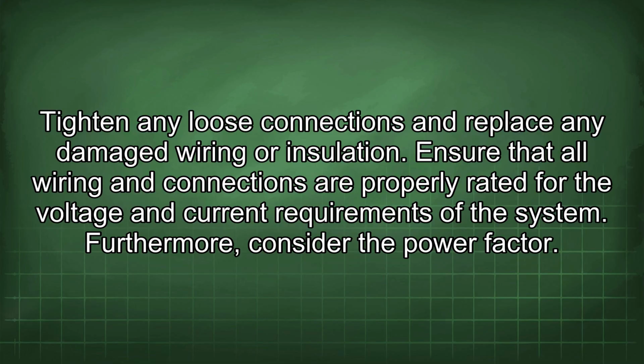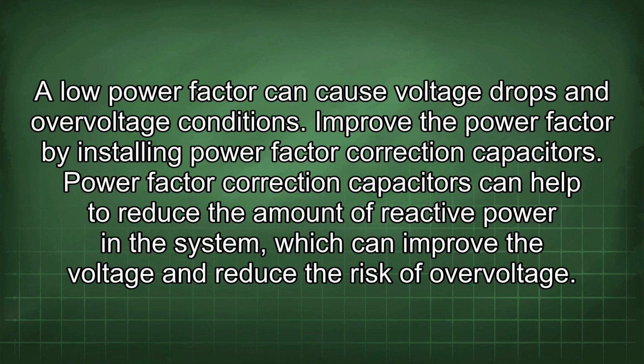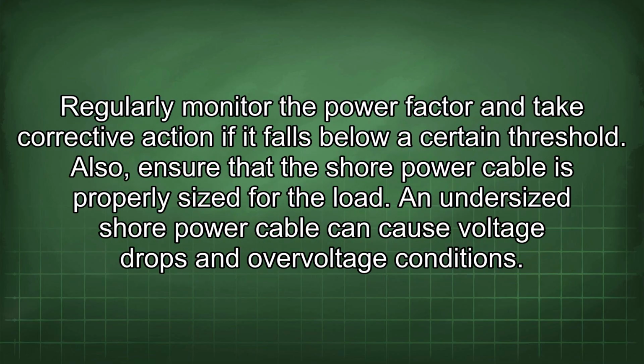Furthermore, consider the power factor. A low power factor can cause voltage drops and overvoltage conditions. Improve the power factor by installing power factor correction capacitors. Power factor correction capacitors can help to reduce the amount of reactive power in the system, which can improve the voltage and reduce the risk of overvoltage. Regularly monitor the power factor and take corrective action if it falls below a certain threshold.